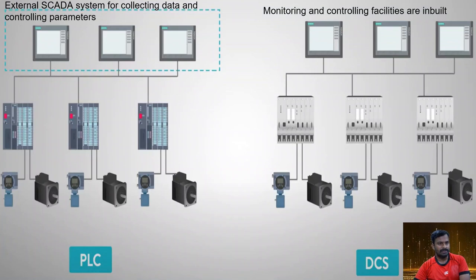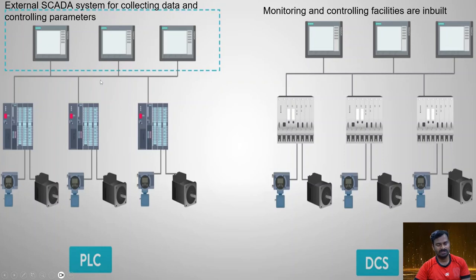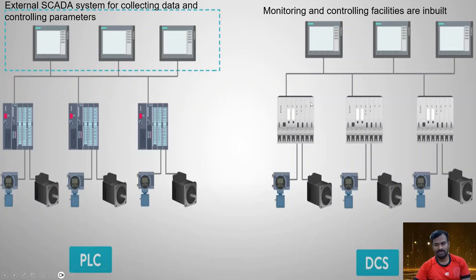A PLC system can achieve similar features to a DCS by using multiple PLCs that exchange data with each other and feed data to monitoring systems. The key difference is that PLC does not have a built-in monitoring system — a separate SCADA or HMI needs to be installed and integrated. In DCS, the controlling and monitoring software come as a single integrated package.